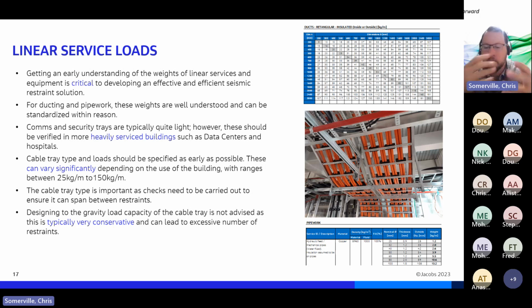Depending on material choice, comms and security trays are typically quite light for most buildings, but in heavily serviced buildings such as data centers, we've got some over 70 kg a meter, so they can get substantial and add a lot of load to your frames. Do be cautious of them and double check them early on.